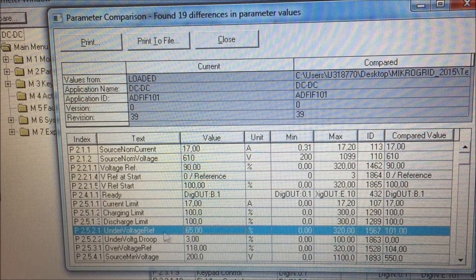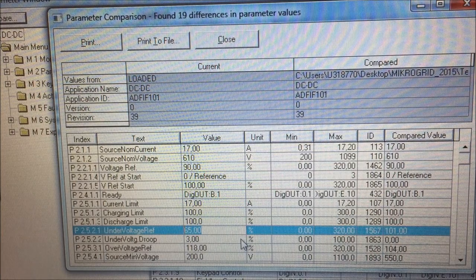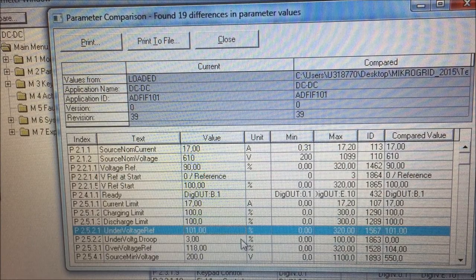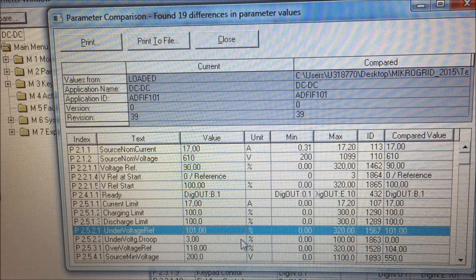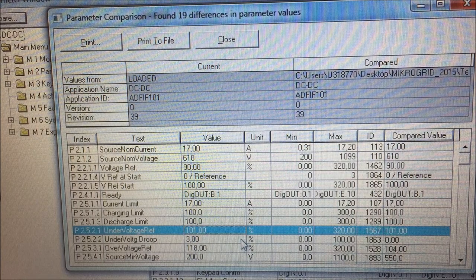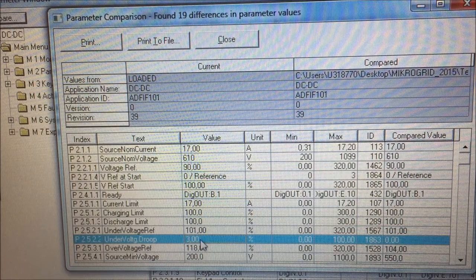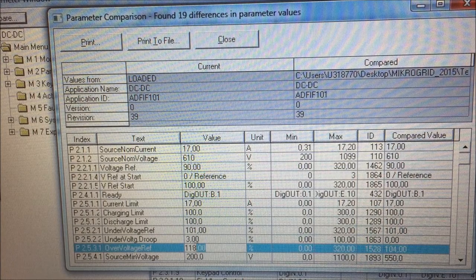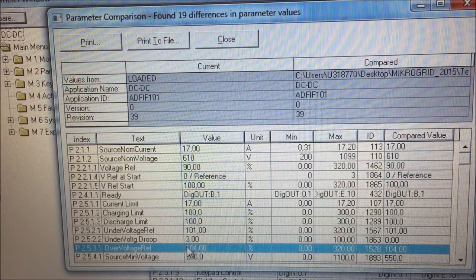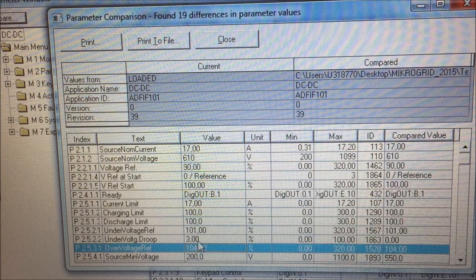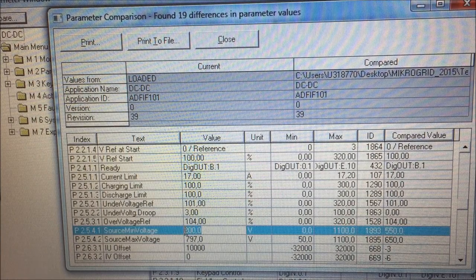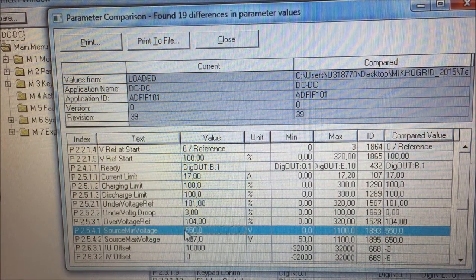My under voltage reference, I use actually to control my DC bus voltage. The principle for controlling the common DC bus voltage from the DC converter is just to bounce it between the under voltage and the over voltage controller. Quite primitive. Under voltage drooping I set to 3%. Over voltage reference, I put to 104. Which means that I'm going to bounce my DC voltage between 101 and 104 with a 3% drooping. The source minimum voltage, I will not allow it to go lower than 550. And the highest I will put to exactly this battery is 650.